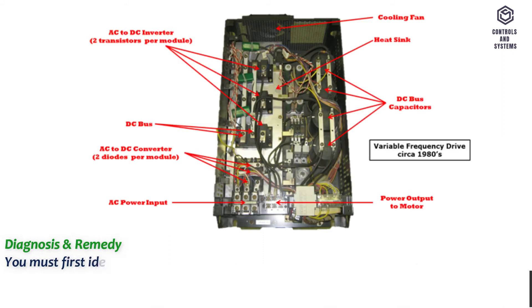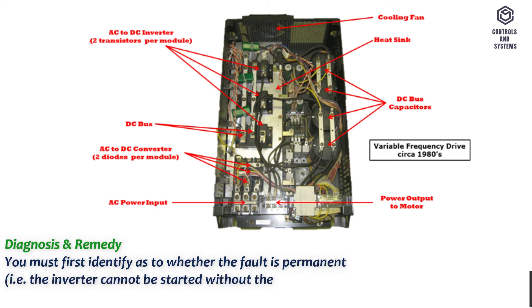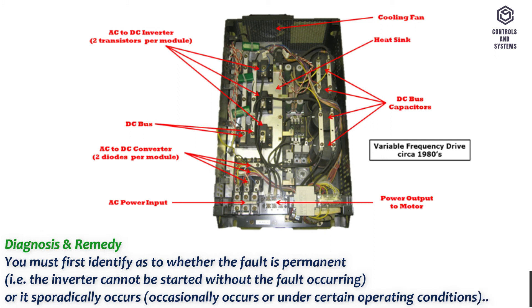Diagnosis and remedy: You must first identify whether the fault is permanent, that is the inverter cannot be started without the fault occurring, or it sporadically occurs, occasionally occurs or under certain operating conditions.